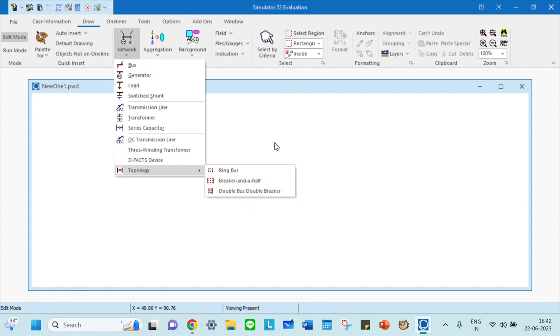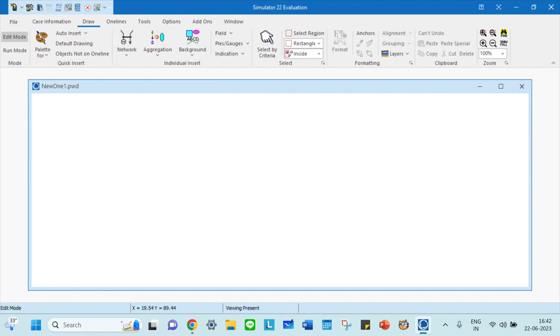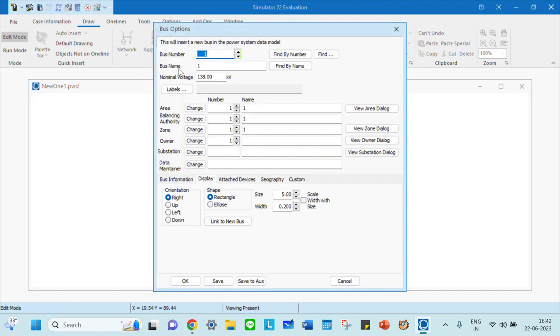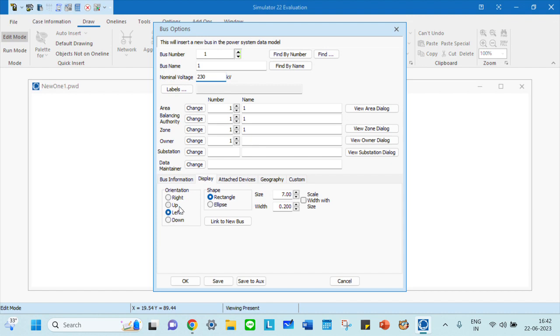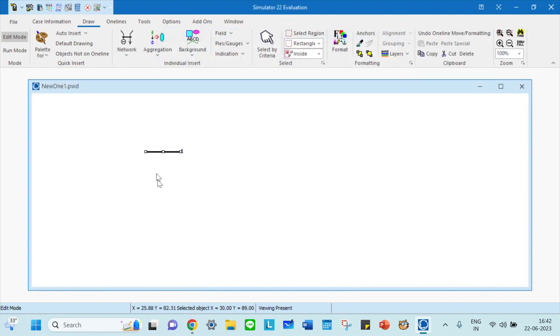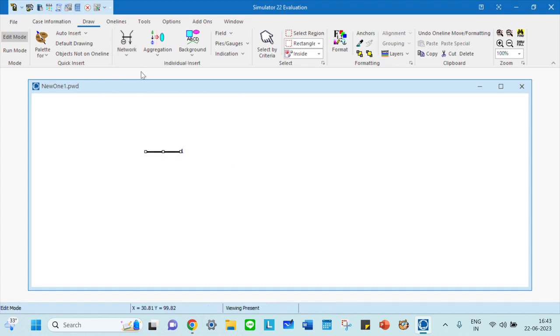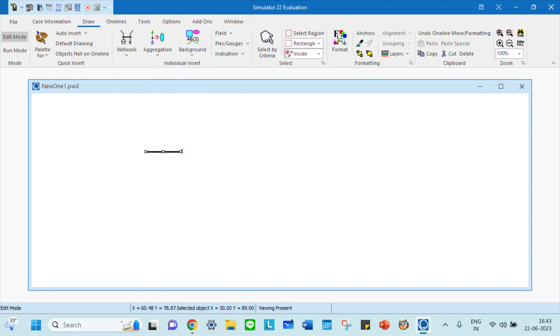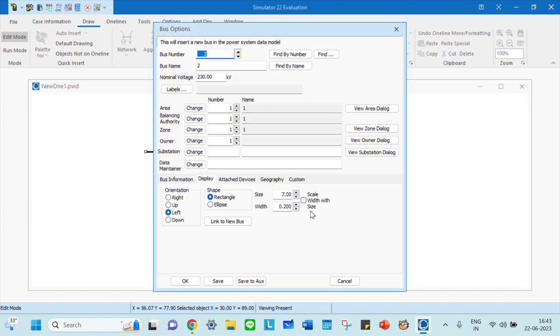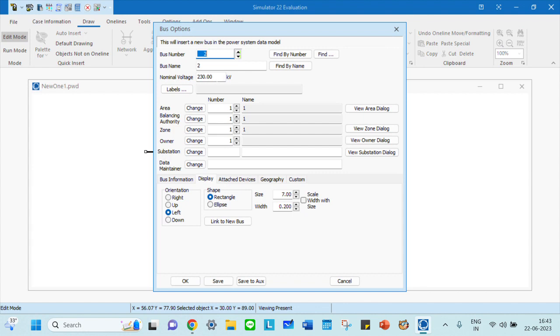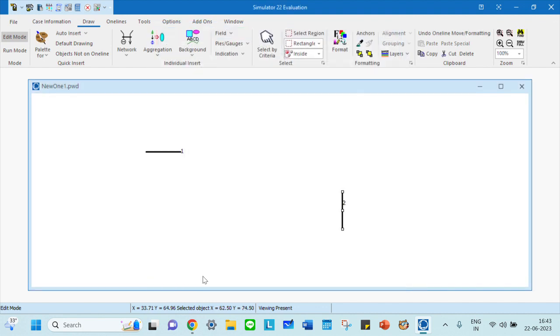Let me draw a quick two bus system. Click on bus and click here. All the details will be loaded. You can give the bus number and voltage - maybe 230 kV. You can see the orientation, whether left side or right side. Save and click OK. Then I want another bus. Since you marked the nominal voltage to be 230, this also comes as 230, but this time instead of left I want it up. Click save and OK.